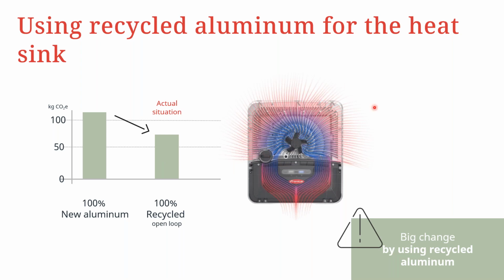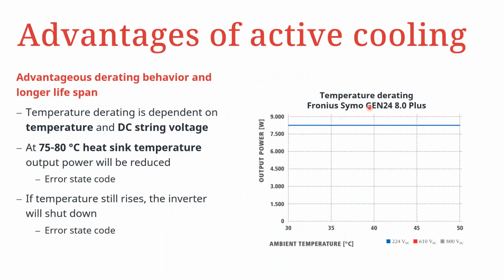So what are therefore the advantages of the active cooling technology? One of the key advantages is that the inverter is able to operate in much higher ambient temperatures, and therefore, as we know, the derating of the inverter is dependent on the temperature as well as the DC string voltage. When the inverter is actively cooled, you keep the electronics inside the inverter within a favorable working temperature range, and therefore the derating happens at much higher ambient temperatures.